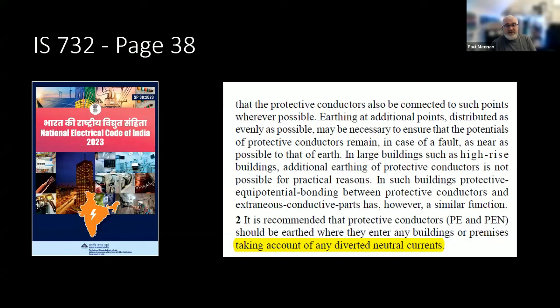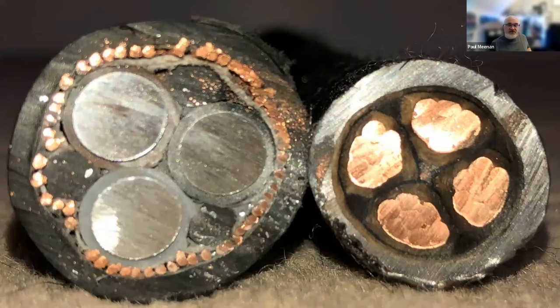Especially if you have a failed neutral on the supply, the more earthing you have, the safer you may be, but you may actually be masking the failure of the neutral because all the network neutral will come into your property. Now, just to show you what it's like in England, this is a picture, one of my favorites. It was taken by me, and the cable on the right is a lead sheathed cable. So this was installed in the 30s.